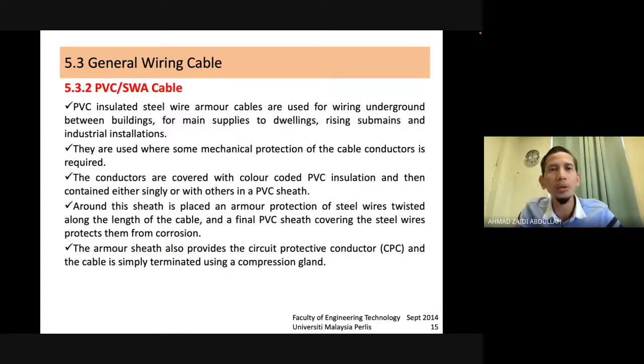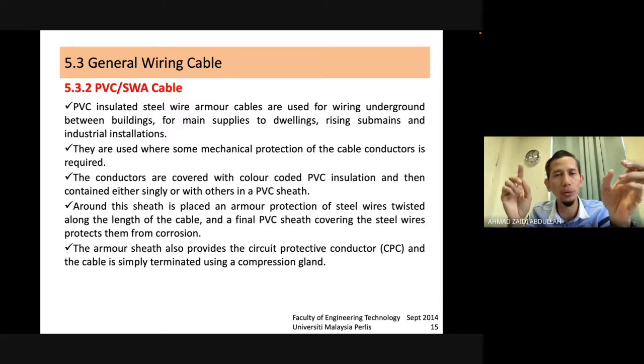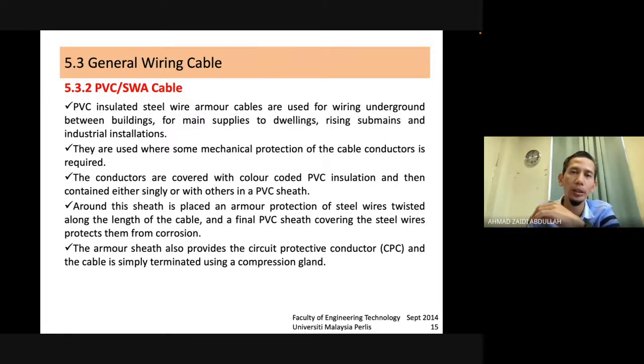So PVC SWA cable, steel wire armoured, is used for wiring underground. Let's say you have 2 blocks that are not connected. If the buildings are connected, it's okay, you can just use PVC, no need for SWA. But if you have separate buildings, then you definitely need to use underground cable. When dealing with underground cable, you select either PVC SWA or XLPE SWA, so you need to find out.